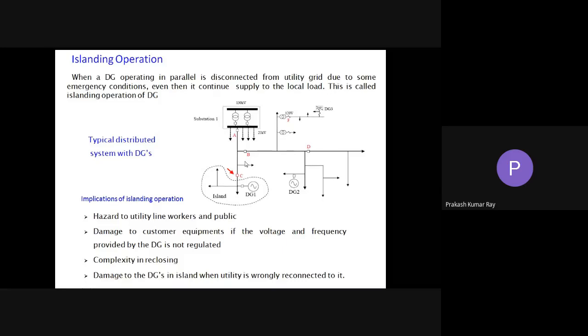Some of the implications I have shown in the slide, like it is hazardous to utility line workers and the public. Somebody is supposed to be doing maintenance in the encircled portion, which I have shown as the isolated network. He will think that the grid is isolated, but DG1 is still supplying power. So when he goes for maintenance, definitely he will get some shock. So this type of event happens in the system while islanding is occurring.